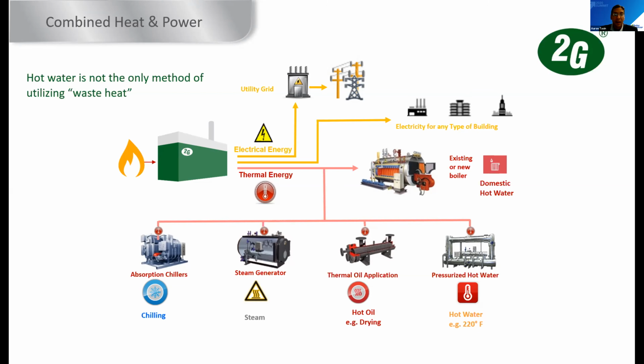Absorption chilling, for those that might not be familiar: with absorption chilling, you're actually utilizing the hot water or potentially even the exhaust directly to the absorption chiller. And through a chemical reaction, the heat is actually creating cool chilled water, whether it's 54-44 like Rich has in the catalog as standard, or maybe 52-42. You're going to hit a limit where you can only get about 39 or 40 as your chilled water temperature out.